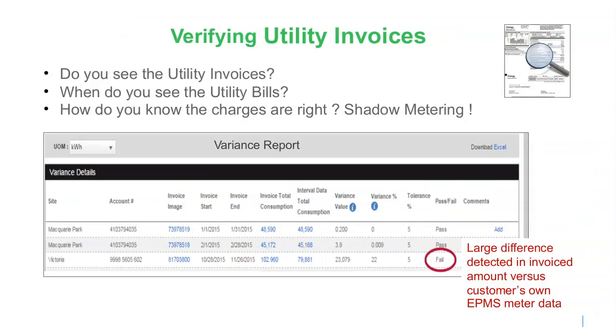So you're looking at your utility bill, and now you have data from your power monitoring system. When there's a customer-owned meter that is looking at the same circuit as a utility meter, we sometimes refer to that in the industry as shadow metering. What we're doing is seeing, do our measurements match the utility's measurements? And when there's a difference or a variance, we want that to be something that's brought to our attention. It is not unusual at all to find systems where there could be mistakes.